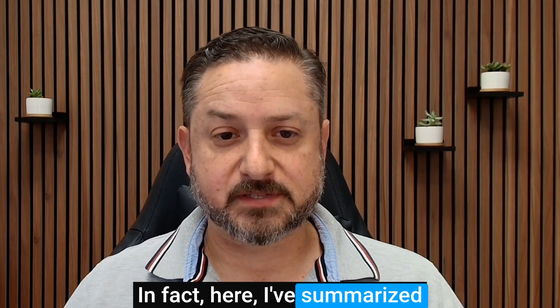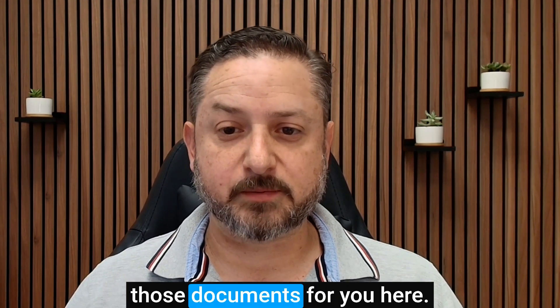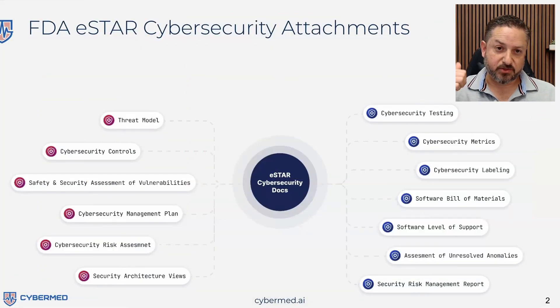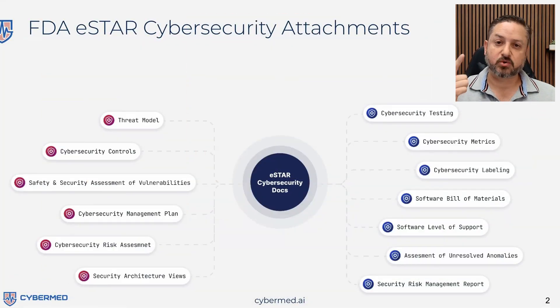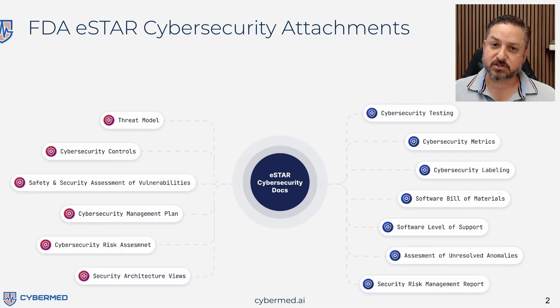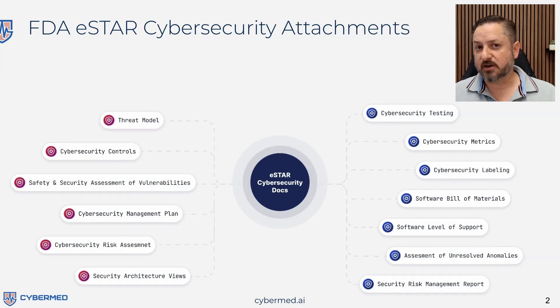Here I've summarized those documents for you. So there's 12 attachments: your threat model, your cybersecurity controls, your safety and security assessment of vulnerabilities, your cybersecurity management plan, cybersecurity testing, cybersecurity metrics, labeling, software bill of materials, software level of support, etc.